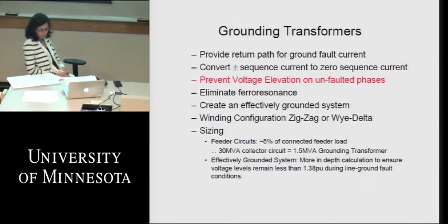The sizing of these transformers is generally about 5% of the current load that you're going to see on that feeder. So if we had, say, 30 MVA, which is the maximum size we can put on generator collectors because of the ampacity of the conductors we use, at 5% this works out to a grounding transformer of about 1.5 MVA for a very large collection feeder. That would be an example of 15 2-megawatt turbines, or maybe 10 3-megawatt wind turbines, to give you 30 MVA.